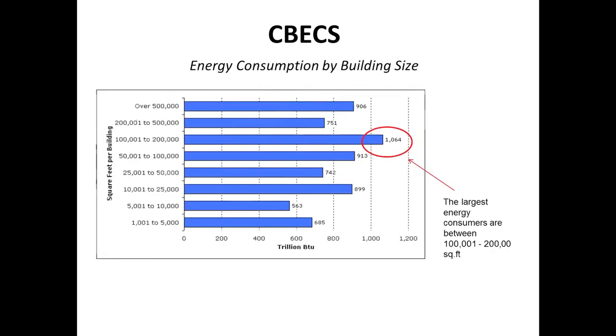If we look at energy consumption by building size, we'll see that the highest energy users are the buildings that fall between 100 and 200,000 square feet. I can confirm that this is where a lot of our work comes. It falls within 100,000 to 200,000 square feet. These are the office buildings that are not quite big enough for a large BMS system that monitors every point, and don't have the financial capital to provide top-rate equipment. In sizes below that, you have a higher intensity, a lot of plug loads, smaller equipment, and there are limitations with equipment. This may be where you have a lot of split AC systems up in the Northeast, where you don't have a high cooling load, so they may be using less efficient equipment.